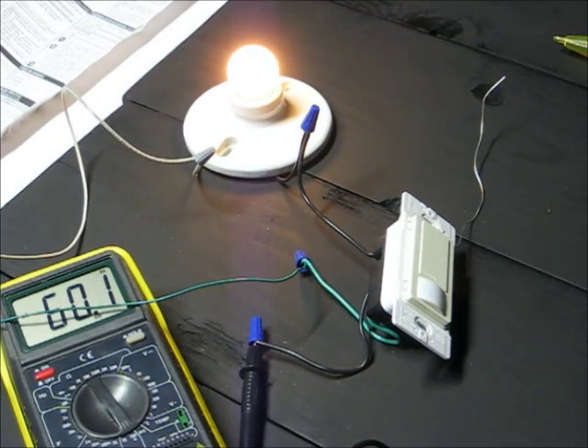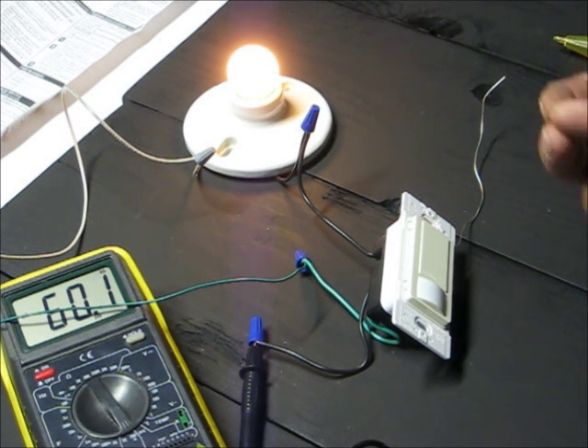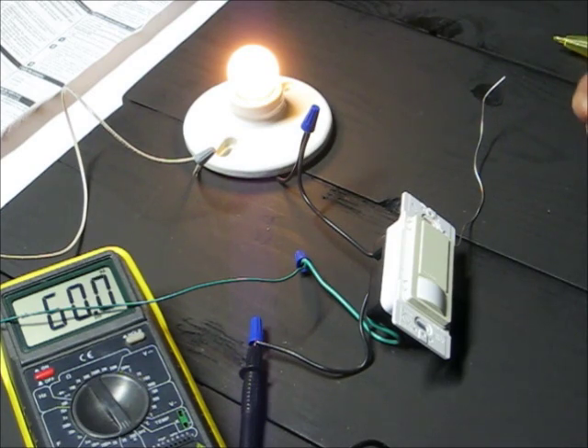While in test mode, this is auto on, and you can hear a relay clicking in it, which means that it's suitable for ballasts and drivers.